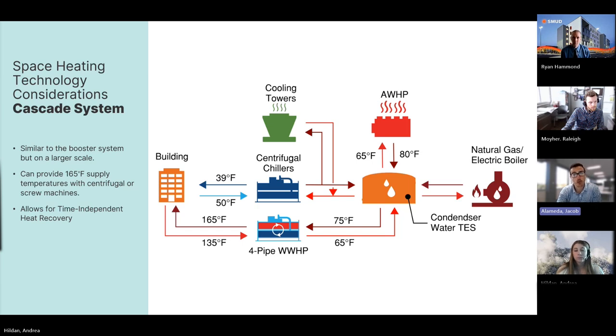I also show here, if you are limited on space or you want a backup for your trim heat pumps, you can have a portion of that trim heat as gas boilers to help provide that trim heat source. And then that would give you a partially electrified system where you're most of the time relying on electric systems. So one huge benefit in this system in general is that it provides time-independent heat recovery. In Sacramento, in this climate especially, there are many days of the year where you need heating in the mornings and cooling in the afternoons, but not necessarily at the same exact time. So this system allows you to store heat and use it later when heating and cooling demand hours aren't necessarily aligning at the same time.